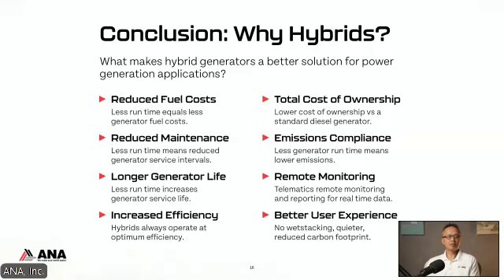So the conclusion on why we want to go with hybrids: it reduces fuel costs, as mentioned in the previous slide. It reduces maintenance - service people are hard to come by, so if you're able to reduce the service intervals from every 3 weeks to every 2 or 3 months, that's a huge improvement. Longer generator life, because you're running the generator less.